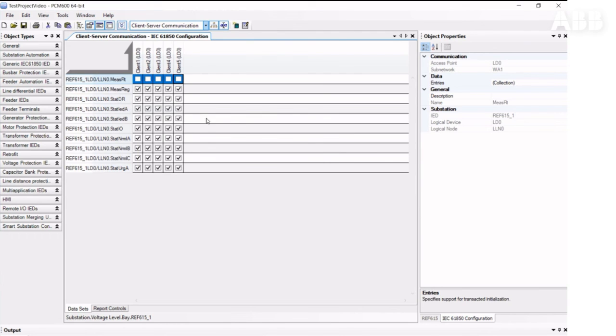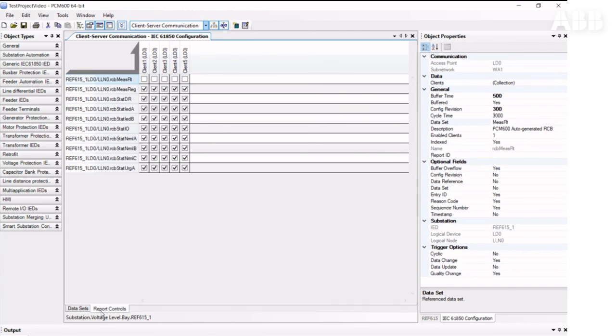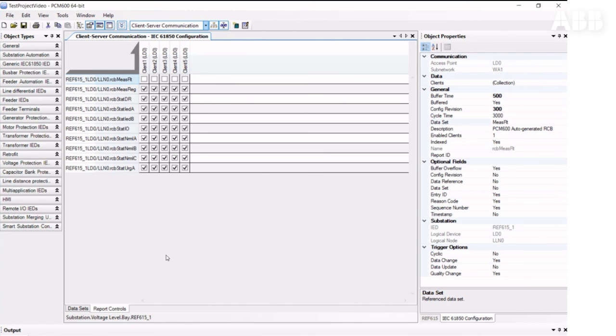It's strongly not recommended to delete datasets for client-server communications, because these datasets are also used for internal event generation, and their deletion may cause problems. So if you do not need to send data to the SCADA or RTU system, the correct way is to unassign this dataset from the clients instead of deleting it.